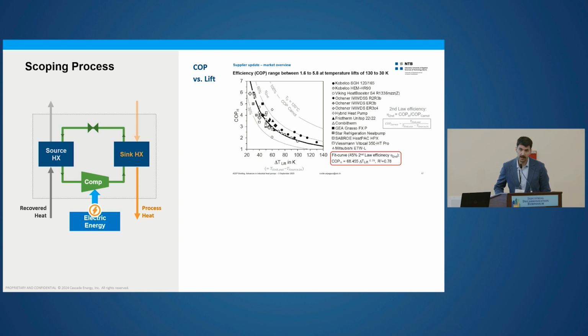When it comes to the analysis, again, keep in mind this was a scoping level effort. We had a couple main assumptions. One of these was around the COP, or the coefficient of performance we used in the analysis. We based it off of this curve fit from actual data from heat pumps, just basing it off of lift, the difference between the source and the sink temperature. With that, we were able to calculate the energy use of the heat pump and subsequently the energy savings.